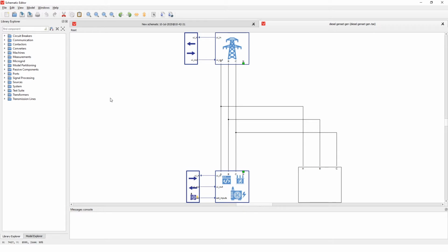The main motivation for this new Diesel Genset component is that compared to our legacy component, it provides easier and more practical parametrization from a system integration point of view. Also, it includes new functionalities expected to be found in real-life applications. These functionalities are overcurrent protection, grid voltage out of range protection, rotor unstable protection, sync timeout protection, and frequency drift. Finally, it does not utilize machine solver in HIL hardware resources. This can help you to create bigger models containing a larger number of generators.